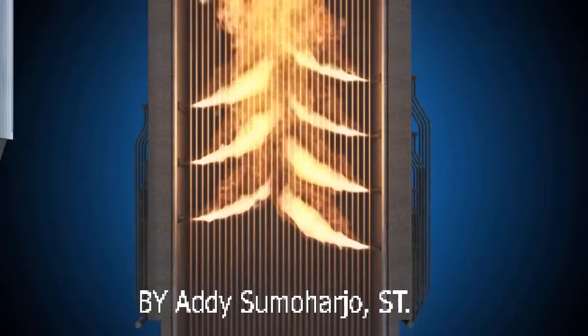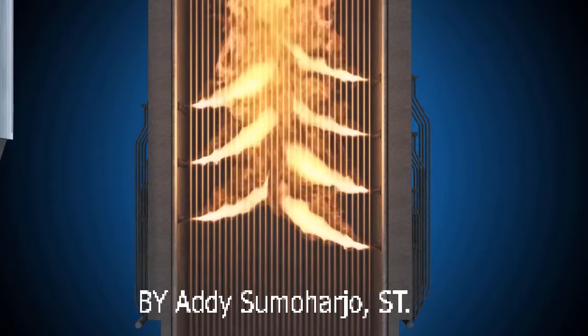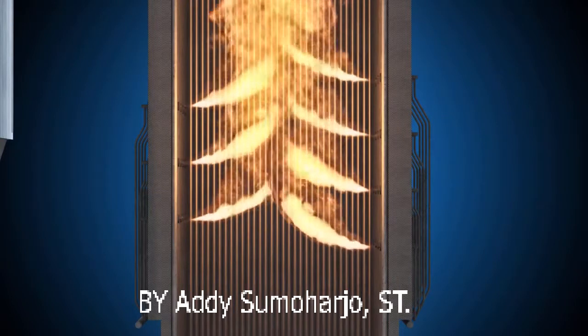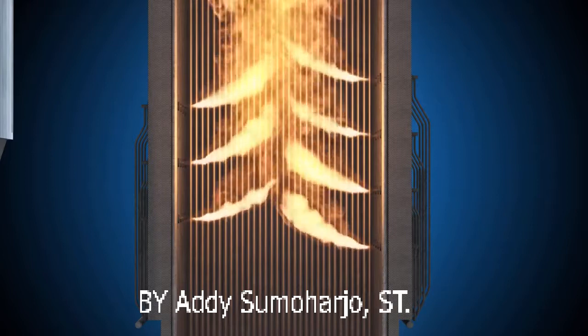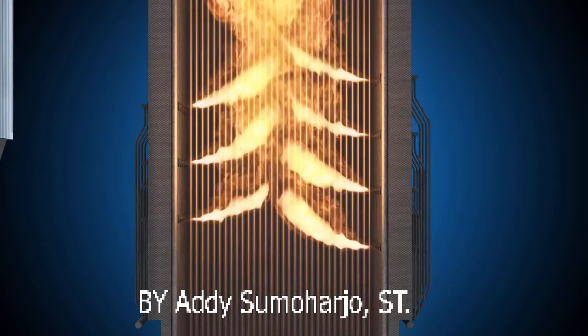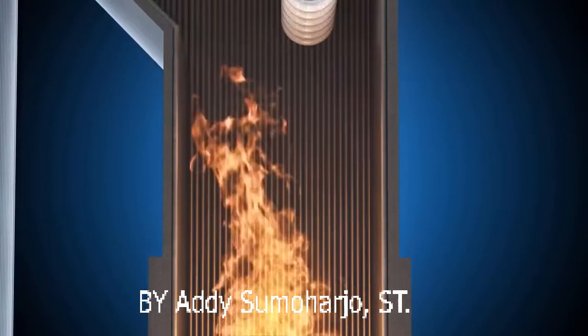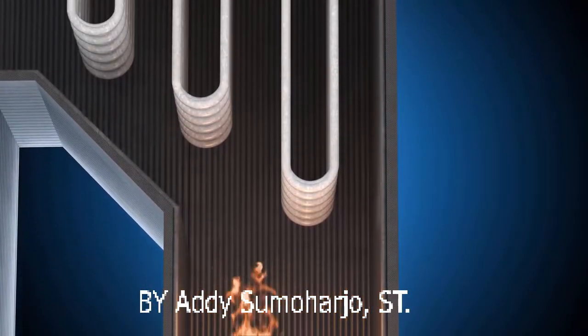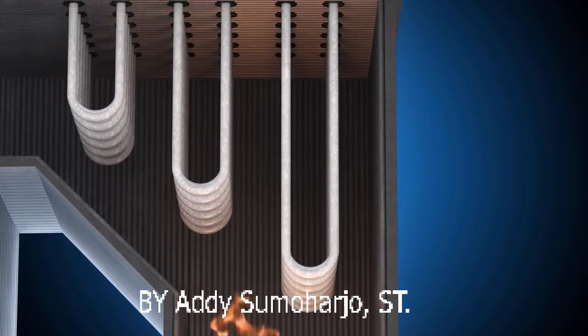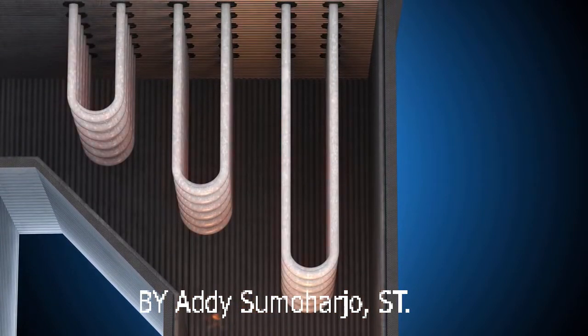When the particles of coal reach the burners, they are mixed with secondary air that has been preheated to over 500 degrees to support complete combustion inside the boiler. The combustion of the coal converts its chemical energy into thermal energy, creating a temperature inside the boiler of over 2200 degrees. That's enough to heat the water in the series of boiler tubes to create steam, which moves onto the turbine to power the next step in our process.